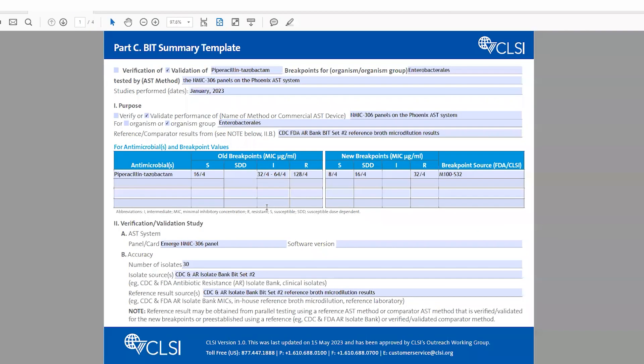I'm going to walk through the template now. I have a pre-filled version that I prepared as an example for this video tutorial. In this example, I'm providing a summary — a validation outline and report — of the validation of piperacillin-tazobactam breakpoints for the enterobacteriales on the NMIC 306 panels on the Phoenix AST system. This was considered a validation because our AST device and system does not have FDA clearance for the updated piperacillin-tazobactam breakpoints with enterobacteriales, so I'm doing a validation study for off-label use.